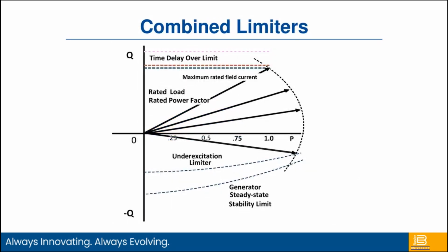When I combine all of those limiters together, if properly set, I can mimic the generator steady state stability limit. So you may be familiar with the generator capability curve, which is another term for this. The generator capability curve shows where that generator's operating range is, to make sure that it's in a safe operating range and not in a damaging situation. So I can tune these limiters to make sure that the voltage regulator, at least, is not operating outside of the safe operating region of that particular machine.